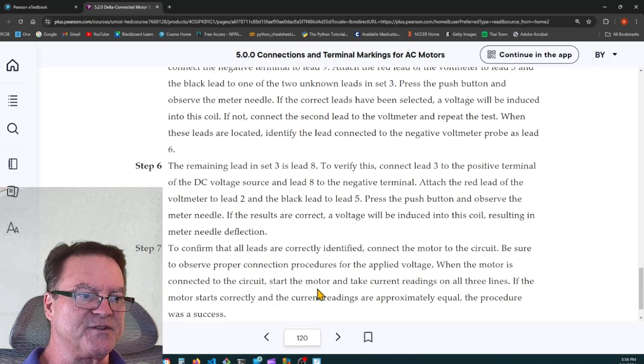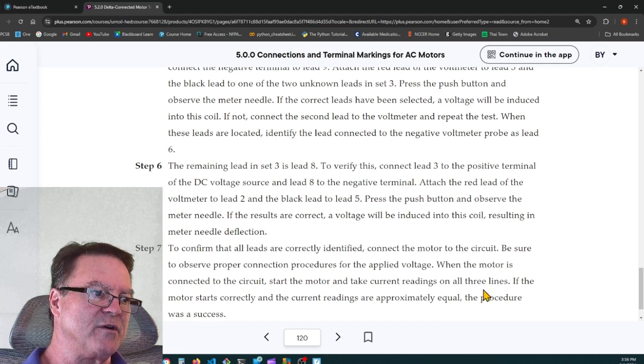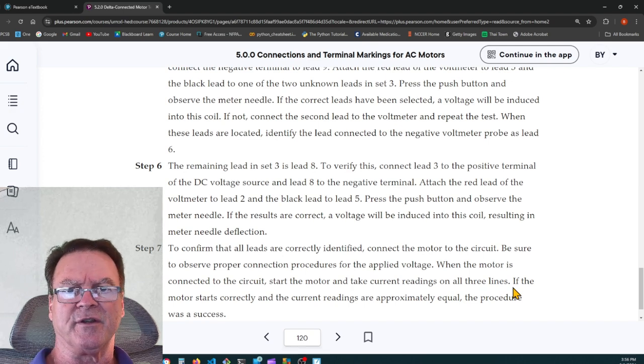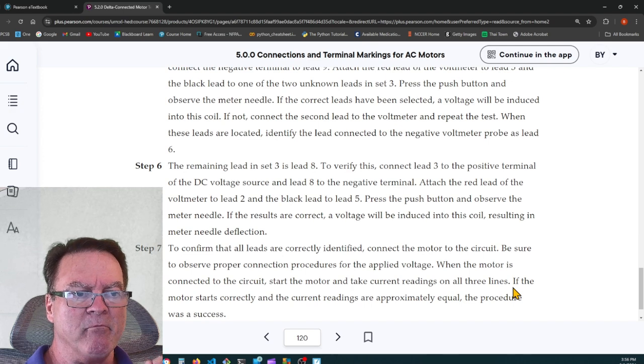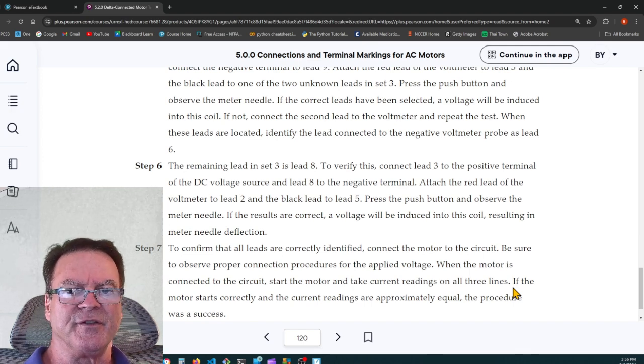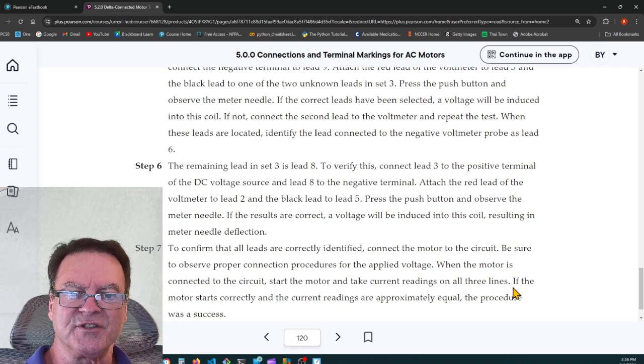When the motor is connected to the circuit, start the motor and take current readings on all 3 lines. What I'm going to say is don't start the motor. Just bump it. Just apply a momentary burst of the 3-phase electricity. If it's 240 volts, hook it up to the 240 and just bump it. Push the start and the stop immediately after, just to see if it rotates.